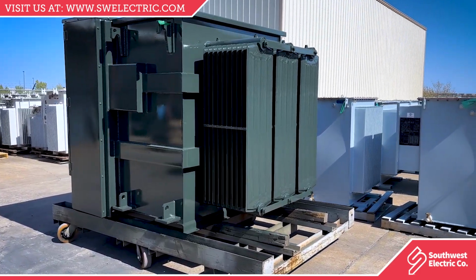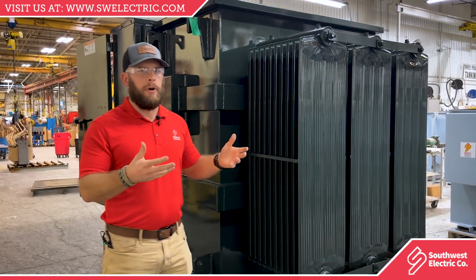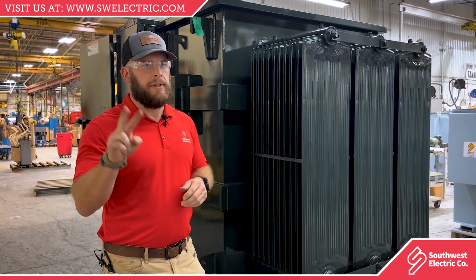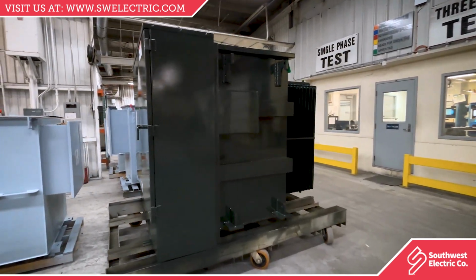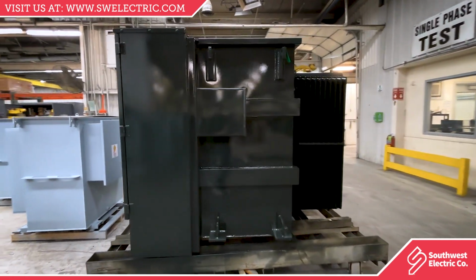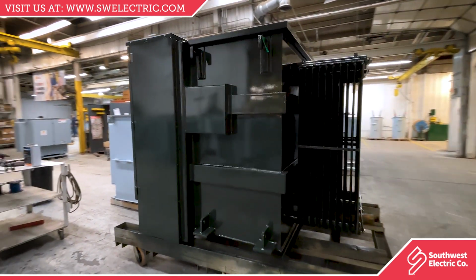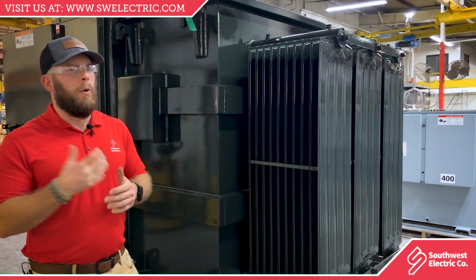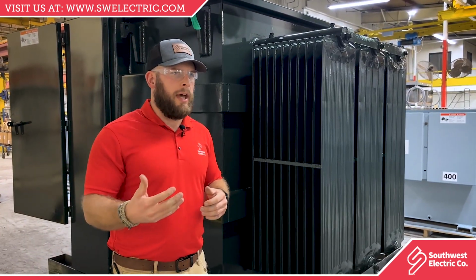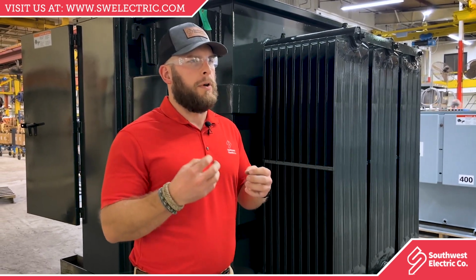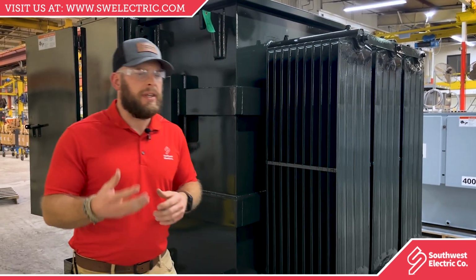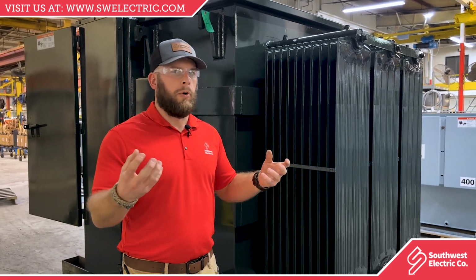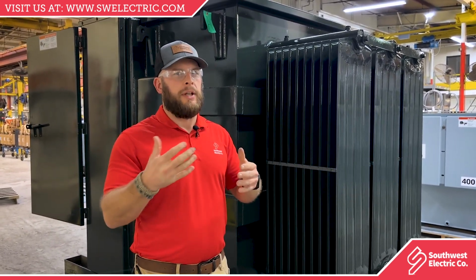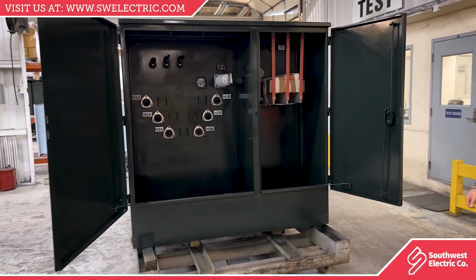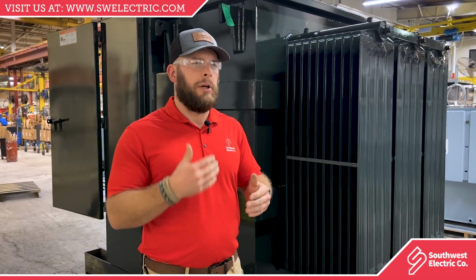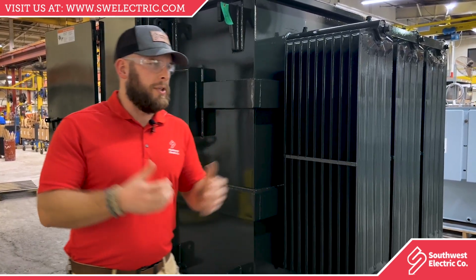And it is exactly as it sounds. The transformer is literally immersed in oil. So that's done for two reasons. First one is cooling. As the transformer is in operation, it will start to generate a lot of heat. And that heat needs to be removed from the transformer. And oil is a very effective way to do that. With your dry type transformers, those are only cooled by air. With oil, the heat capacity increases, so it can hold more heat and it can dissipate more heat to keep that transformer cool. Because if the transformer starts to get too hot, it will start to do damage to the insulation and will start to impact the life of the transformer, which we don't want.